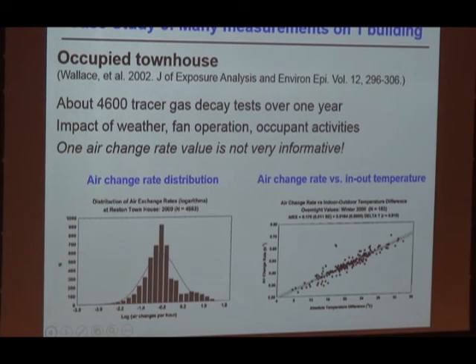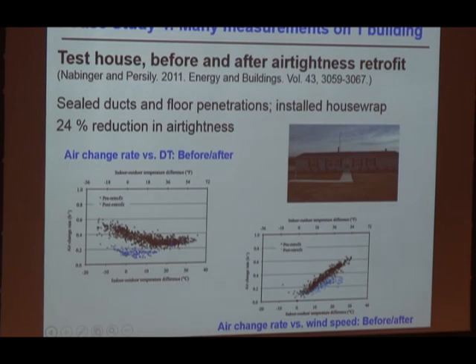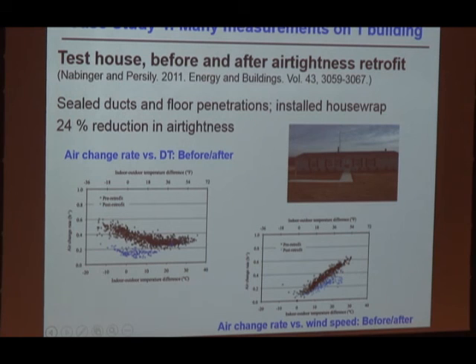The third case study involved nearly a year of measurements in a townhouse, examining the impact of weather, fan operation, and activities — a big dataset. The air change rate as a function of temperature difference showed the expected relationship, but any one measurement is just one data point; you need a variety of conditions to really understand a building. The fourth case study measured infiltration rates before and after an air tightening retrofit, with plots of air change rate versus temperature difference and versus wind speed clearly showing the effect of the work.